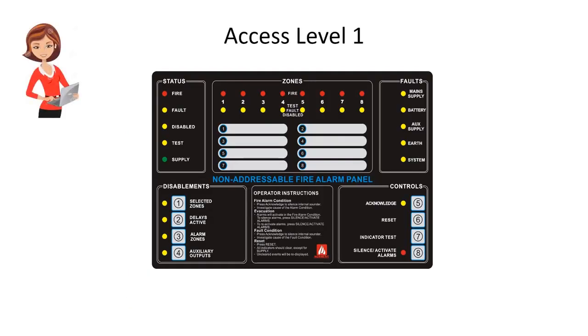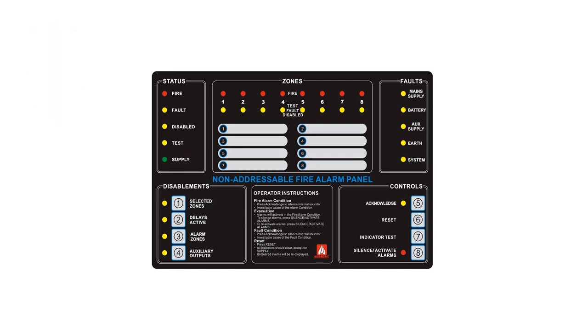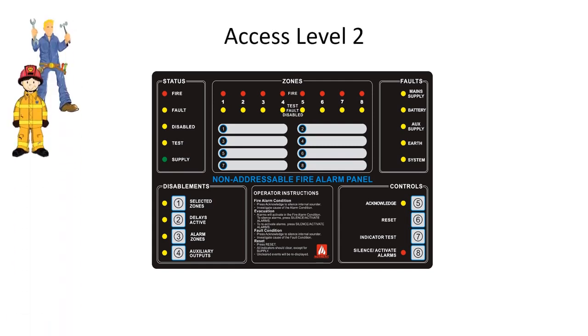Access Level 1 is available directly at the panel and requires no special entry. To enter Access Level 2, check that there are no unacknowledged events on the panel, then press the Acknowledge button for 3 seconds. The supply LED will flash rapidly. This allows the entry of the Access Level 2 passcode. Press 6688. You will notice that the first 4 detection zone yellow indicators will light with each button press.